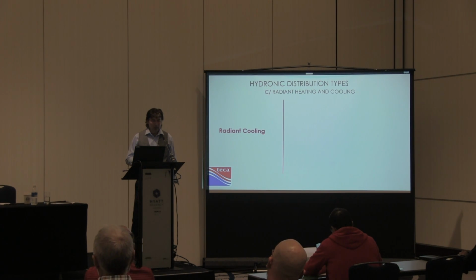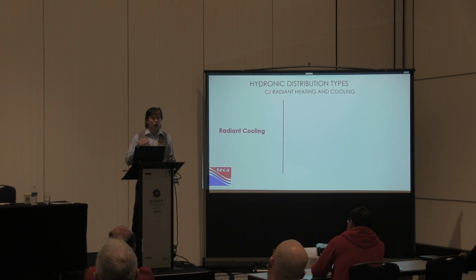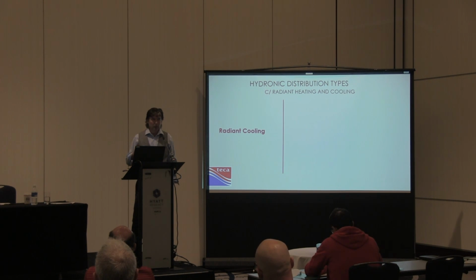But when we're talking about heating a room, concrete itself has a thermal resistance, which we calculate in. If you say, well, it's a bedroom upstairs and I'm going to have some underlay and then I'm going to have this wool carpet or whatever, each of these things has a resistive value that has to be put into our calculation software. Now, you can dramatically screw up the ability to heat a room by using underlay and carpet. Underlay is about the worst, and carpet's after that. So it's critical to look at that.